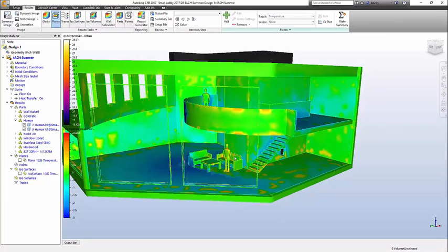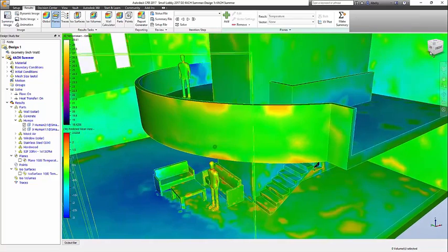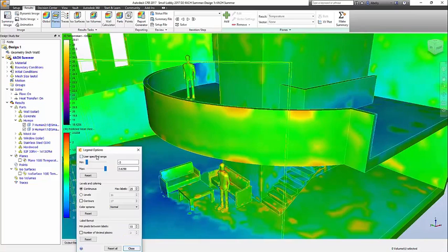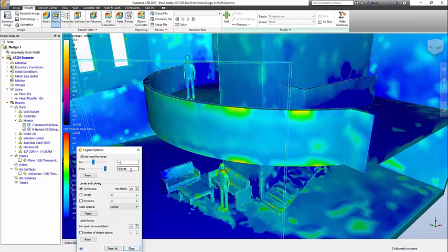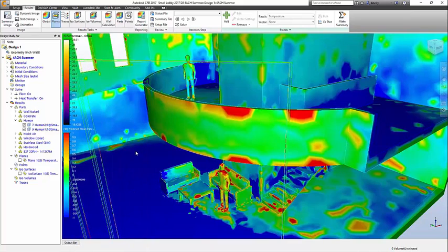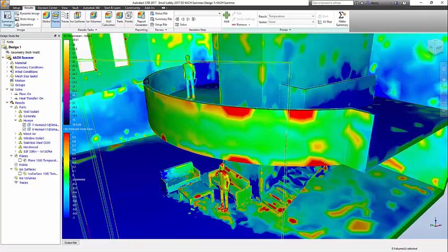Thermal comfort is evaluated by a predicted mean vote rating between minus 3 and 3, where minus 1 to 1 is the desired target. This simple rating takes into account everything, and is a great leading indicator. Here it is clear that the person downstairs is a bit on the hot side at 4 air changes per hour.